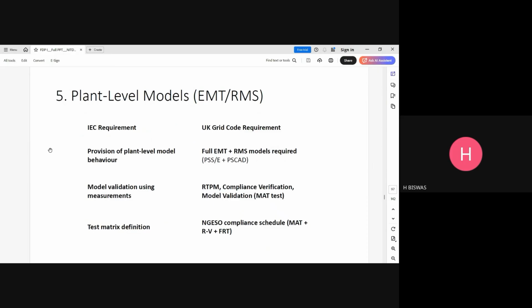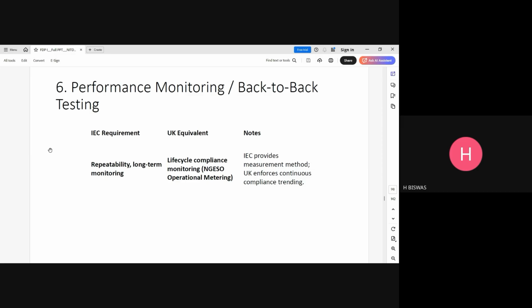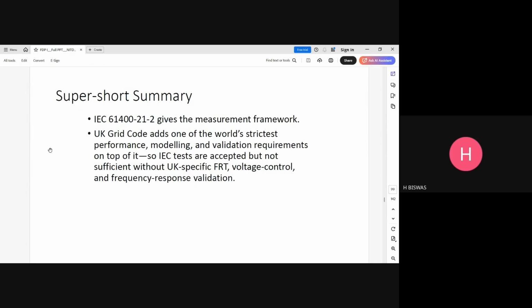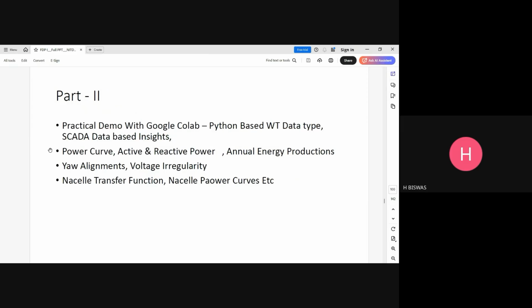Plant level models, EMT, RMS, again something like that. Performance monitoring, back-to-back testing: the IEC requirement is specific, and the UK requirement is, again, a little specific. So, in general, a super short summary: 21 part 2 gives a measurement framework. The UK grid code adds one of the world's strictest performance modeling and validation requirements on top of it. So IEC tests are accepted, but are not necessarily sufficient without some of the UK-specific tests.